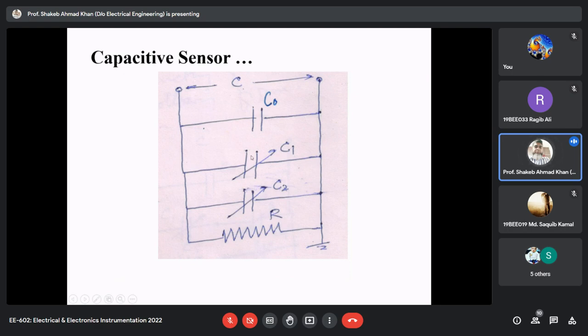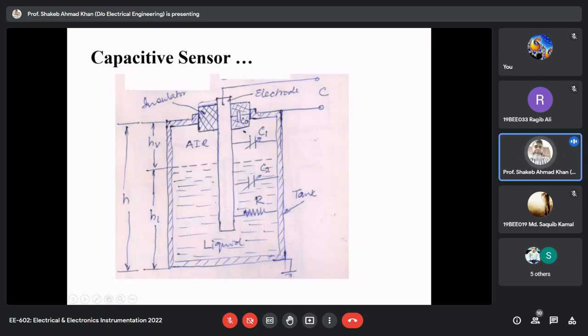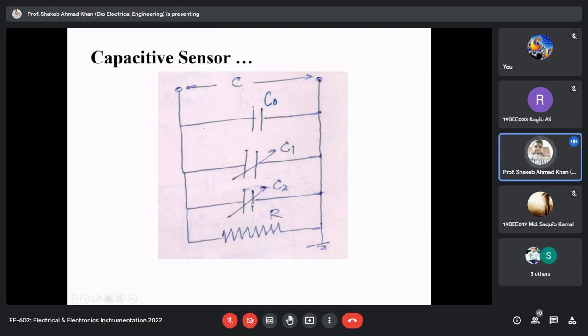So the equivalent circuit: these two capacitances are variable, one for the air, one for the liquid level. This is your cork capacitance - the cork is insulating material between the two electrodes, so its value will be constant, and this is the resistance of the insulating material. This C2 is for the liquid.